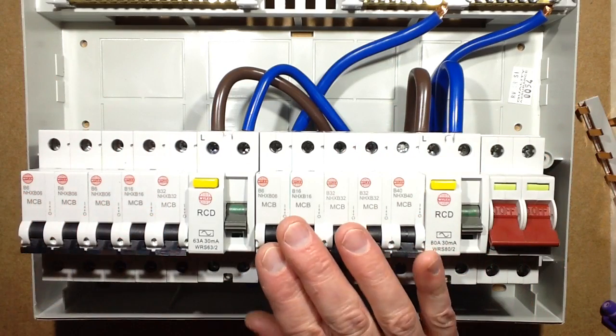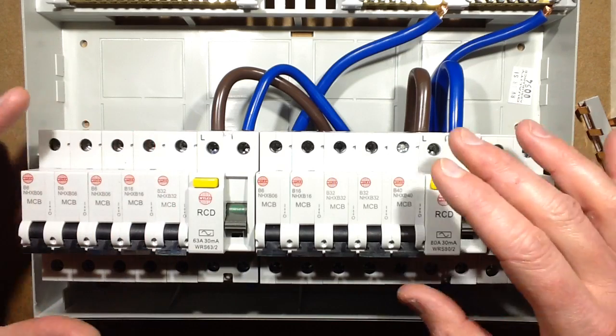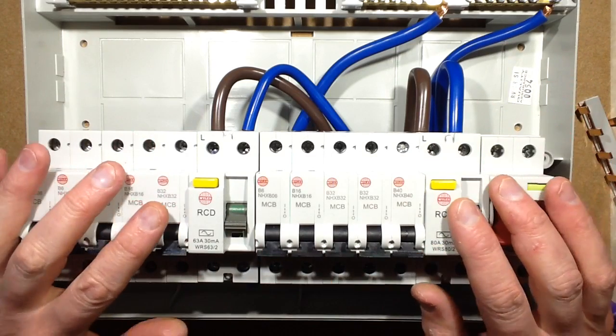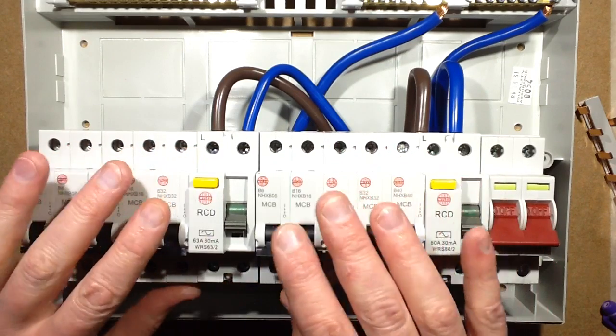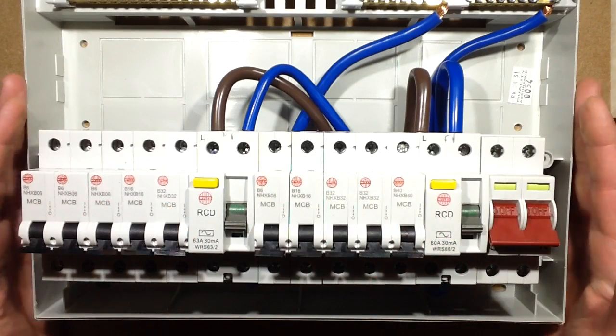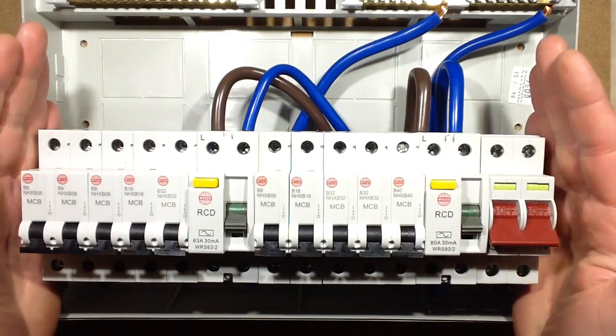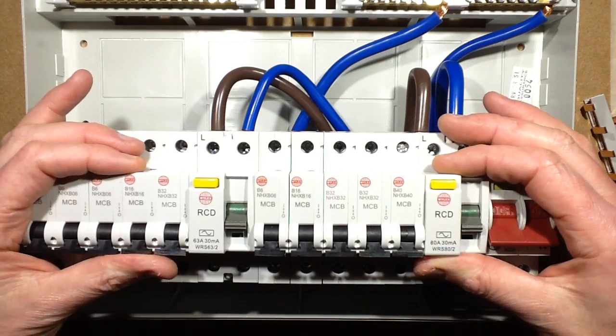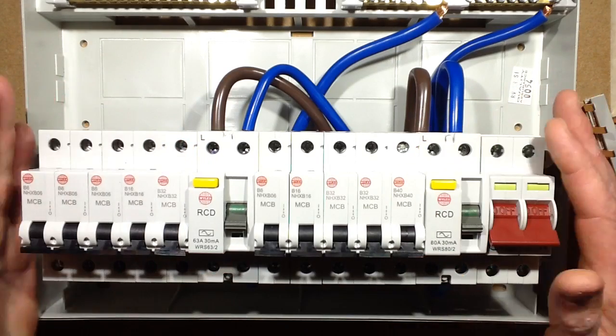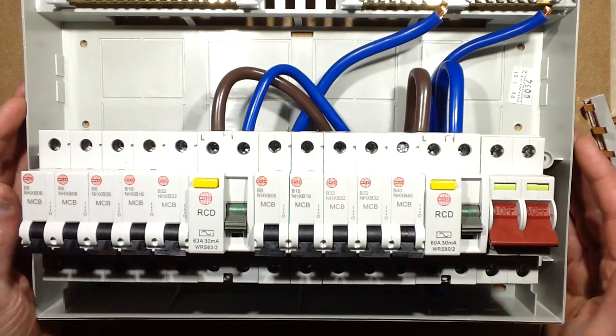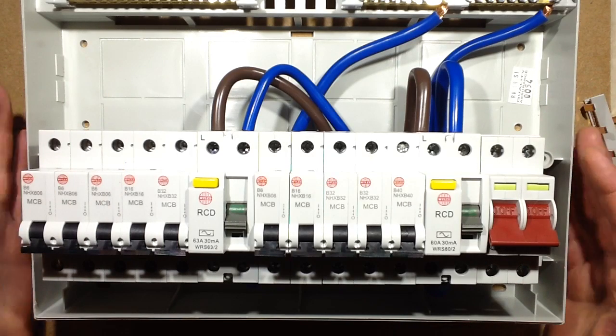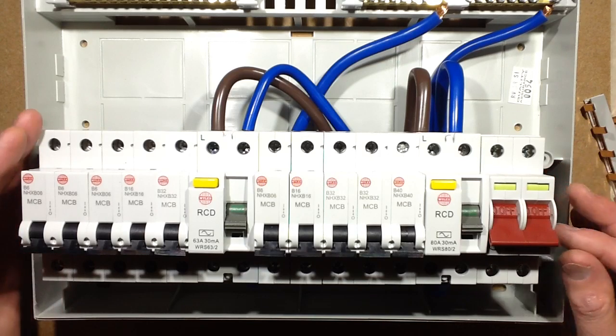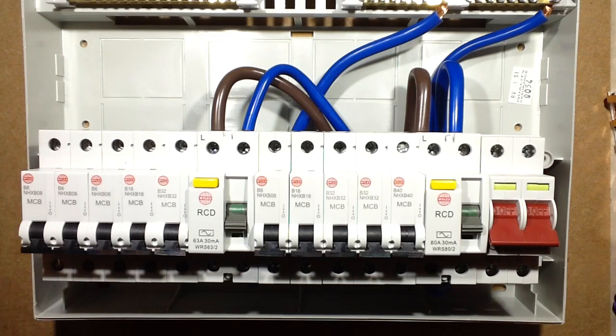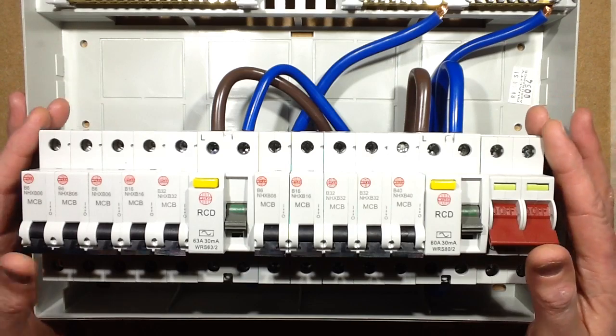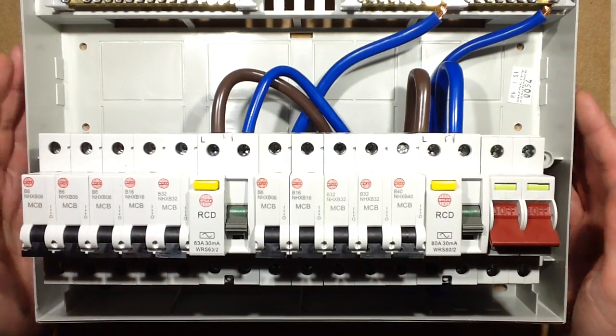So this is a typical arrangement in the UK now, that you can mix and match breakers. You can say, I'll have lighting and power downstairs and lighting and power upstairs. And it means that if you have an earth leakage problem in your house, it's not going to just kill power to the whole house, which was what used to happen, and what certainly happens to this house when there's a fault, because this house is still protected by one main RCD. That's partly because the electrical utility company supplies that, purely because they want the power. If they have an outage in the local neighbourhood, they want the power to my house to go off completely, so that when they close the power in at local small substations, the load is picked up slowly as people reset their breakers. I think that's ultimately why they do it. It's also a good safety feature, as common with rural electrical supplies.